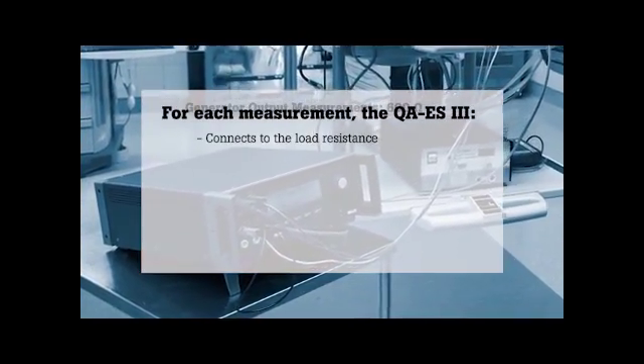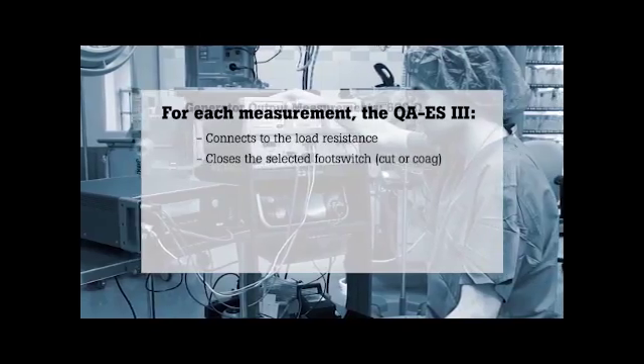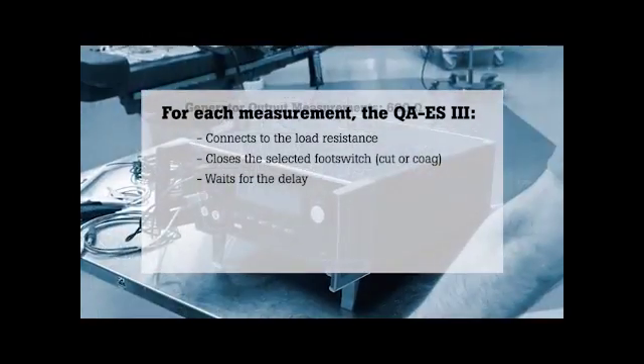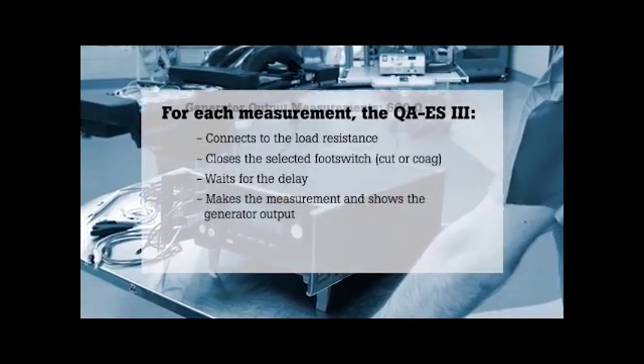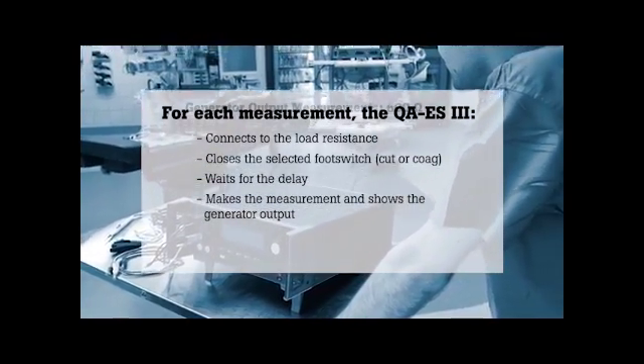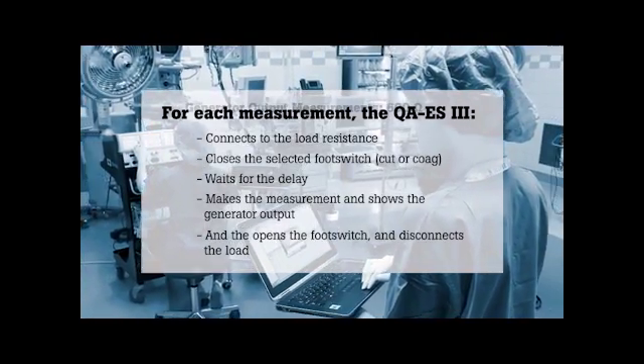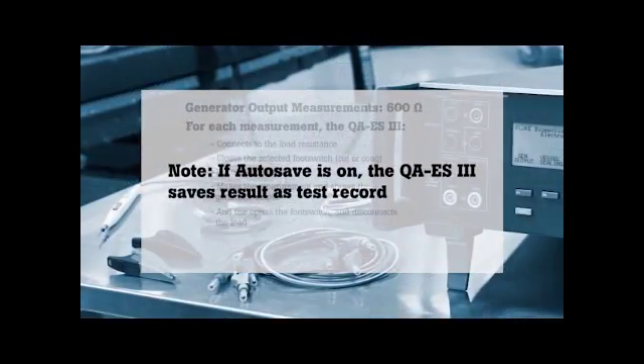connects to the load resistance, closes the selected footswitch (cut or coag), waits for the delay time, makes the measurement and shows the generator output, then opens the footswitch and disconnects the load.